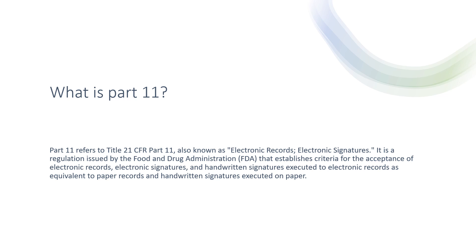Part 11 refers to Title 21 CFR Part 11, also known as Electronic Records and Electronic Signatures. It is a regulation issued by the FDA that establishes criteria for the acceptance of electronic records, electronic signatures, and handwritten signatures executed to electronic records as equivalent to paper records and handwritten signatures executed on paper. For example, if you are using records in electronic format instead of hard paper, and signing electronically instead of manually with a pen, then Part 11 regulations shall be applied.